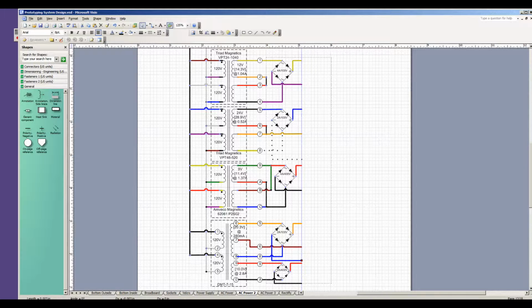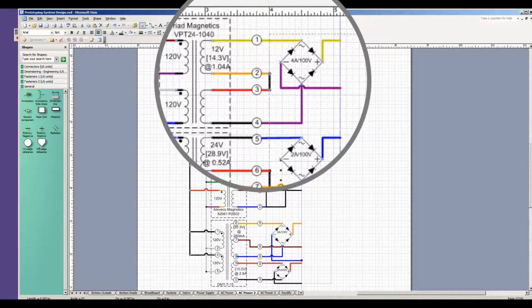In my so-called mind, bearing in mind that I'm not a professional electrician, and I'm sure that professionals would have a much clearer idea of what to take a look at and what formulas to use and so forth. But when I'm looking at, according to the manufacturer, a 24-volt secondary, that's 24 volts RMS. Now, I'm interested in peak voltages. As I recall from high school physics, to convert RMS to peak, you multiply by the square root of 2 or something like that. I'm not sure exactly what the derivation is. I probably knew it at one point in time. I'm sure that a professional electrician would know it. 24 times the square root of 2 works out to about 33.9 volts. And that is the peak voltage for the first secondary.